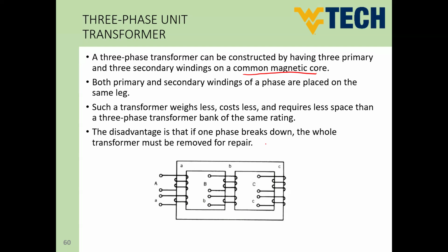Another thing, as we mentioned in the open delta connection, if you already have a delta-delta transformer, you still can keep your load working at 58% of its rating. So you don't need to disconnect the transformer completely for repair. So this is one drawback in the three-phase transformer core.